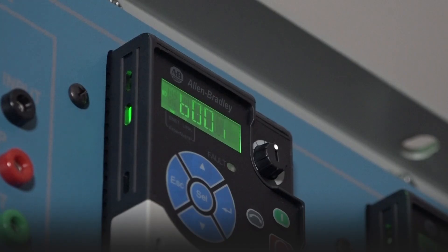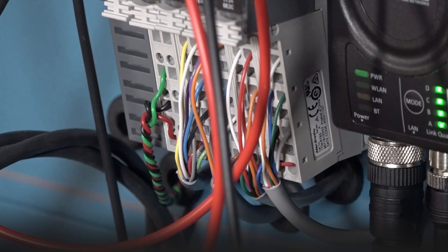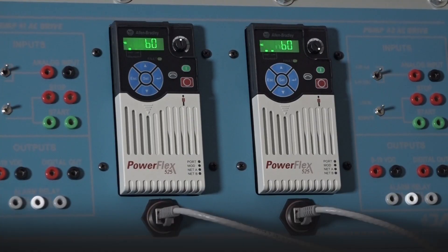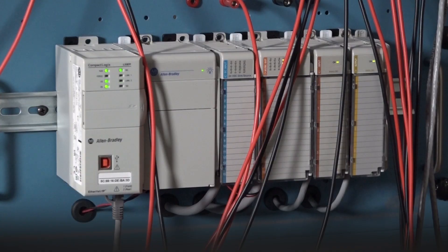So this uses a software called PlantPAx by Rockwell Automation and that's our distributed control software that powers all the controls of the system. Each pump is controlled by a variable frequency drive, a Rockwell PowerFlex 525. We also have a process rated PLC which is a CompactLogix Allen Bradley PLC that's modular based so we can add different applications to it as we grow.